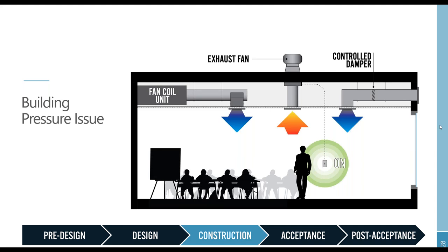And what we then discovered was they had not installed an actual motorized control damper. Instead, they had installed just a backdraft damper and not adjusted the weight on it. So what happened in this case was, if the fan coil unit was on, then it would overpressurize the room and the doors to the space would not close because the pressure inside the room was too high.